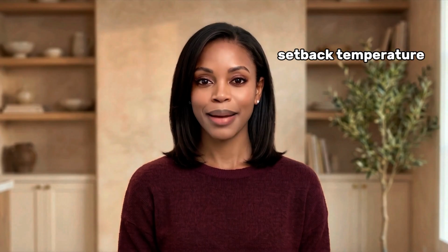Setting 4, setback temperature. Let's say your normal room target is 20 degrees Celsius. At night, you don't necessarily want the same temperature, so your controller allows a lower target. That's a setback. For example, you might have 20 degrees Celsius during occupied periods and 18 degrees Celsius during a reduced temperature period, whatever number works for your house.